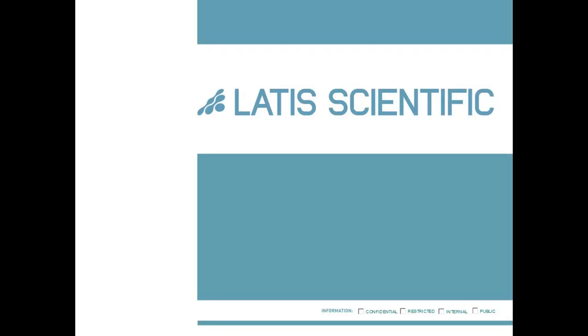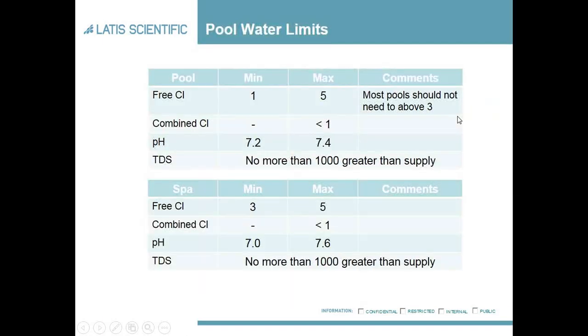So what are the pool water limits? For swimming pools, the limits for free chlorine are one milligram per litre to a maximum of five milligrams per litre. Most pools won't really need to go up to three as long as filtration is working well and being backwashed regularly and not being overloaded. The combined chlorine you would always want to be less than one.